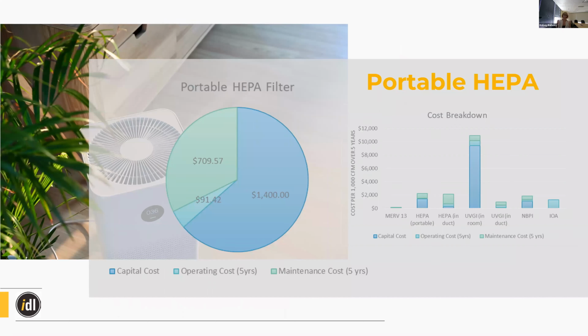And then what that came out to for us was, like I mentioned, high capital costs, just because buying the portable filter can be pretty expensive. And the HEPA filters within the portable unit can be expensive to replace, but operating costs are pretty low. So once you do that capital cost, the portable HEPA filters give you a lot of flexibility. You don't have to turn them on, and then you don't use any energy. So I like them for that reason.